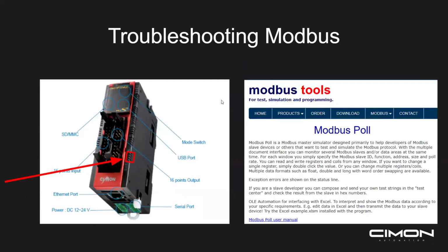Okay, so troubleshooting tips for the PLC. On the bottom right-hand side, this is not exclusive to Modbus. This is for any type of communication you're doing with the PLC. So if you're using serial on the PLCs, you'll notice that there are 4 LEDs at the bottom right-hand side of the PLC that will illuminate and flash very quickly or rapidly, right?